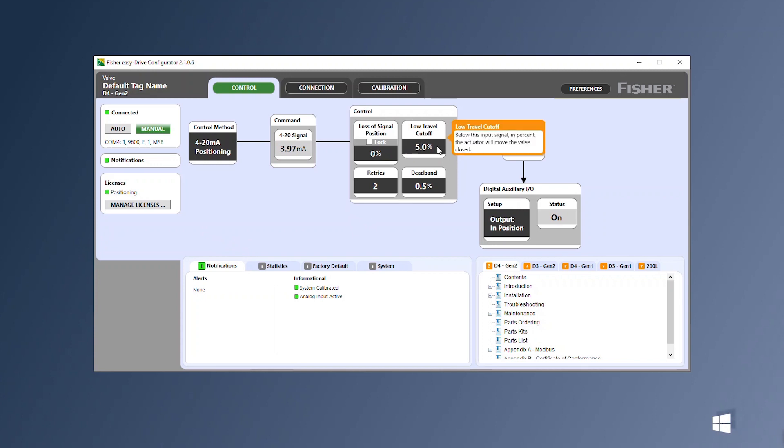The low travel cutoff is the minimum position setting the valve will move to before moving fully closed.